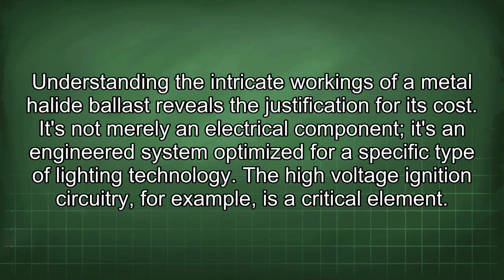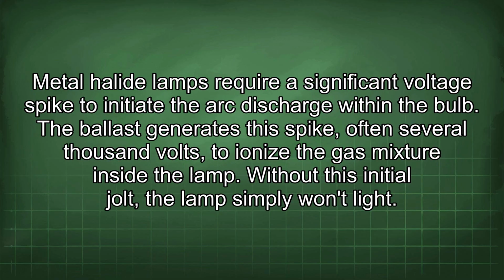Understanding the intricate workings of a metal halide ballast reveals the justification for its cost. It's not merely an electrical component, it's an engineered system optimized for a specific type of lighting technology. The high-voltage ignition circuitry, for example, is a critical element. Metal halide lamps require a significant voltage spike to initiate the arc discharge within the bulb. The ballast generates this spike, often several thousand volts, to ionize the gas mixture inside the lamp. Without this initial jolt, the lamp simply won't light.